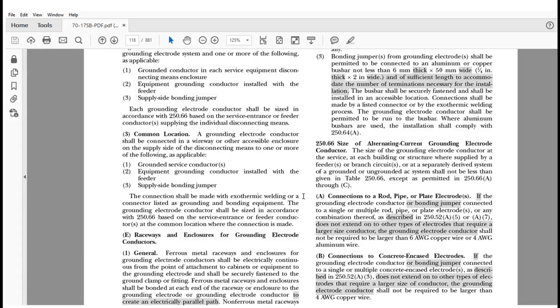So with that daisy chain approach, they have changed that for the 2017 code to make it a little easier to understand, and I think they did a good job. So let's look at it. The intent of this change, which was a revision, is that the term sole connection for sizing grounding electrode conductors to specific grounding electrodes has been removed and revised. And it also made it real clear.